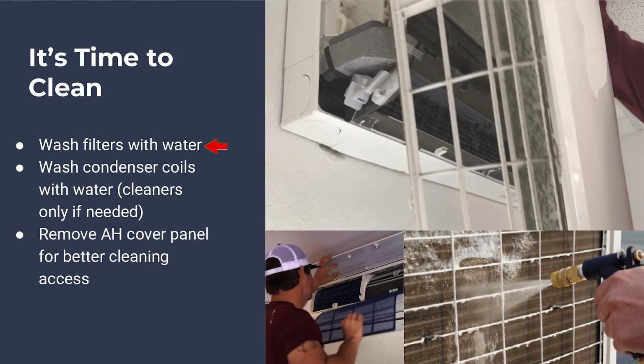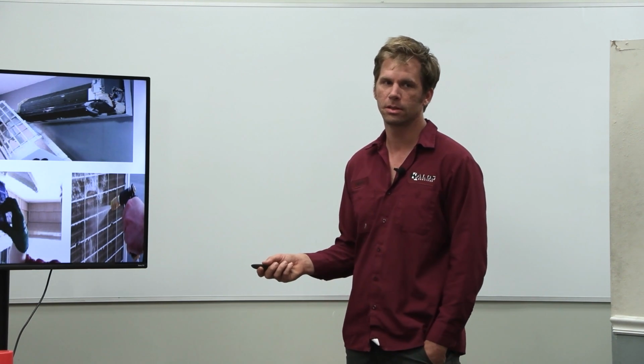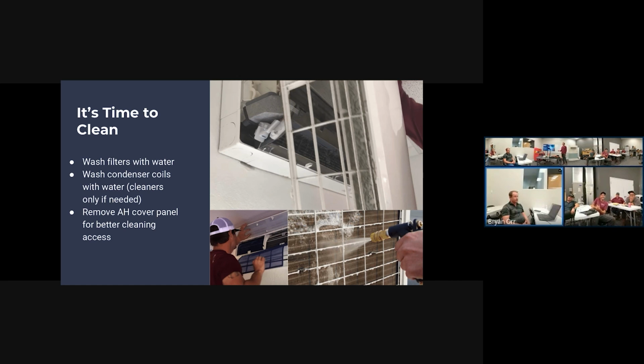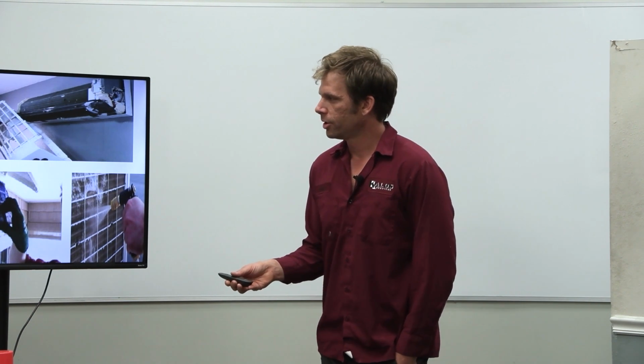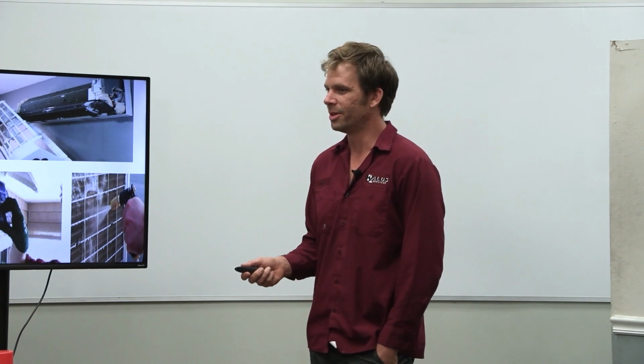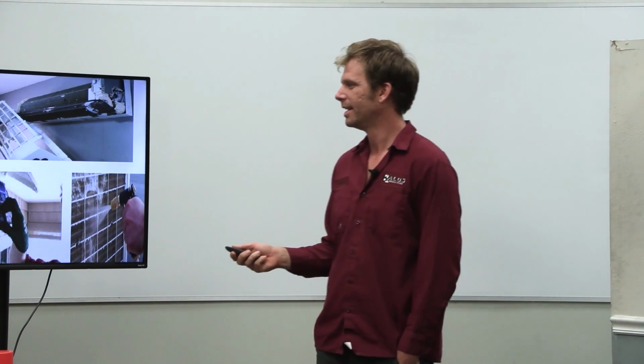Okay, so wash your filters with water, and your condenser coils don't typically get that dirty unless you're in an area of really high dust. Commercial applications, barns, animals, like my dog who lays up against it, dryer vents. Dirty children, in your case. No, the dirty children do not get the condenser coils dirty. It just doesn't happen.